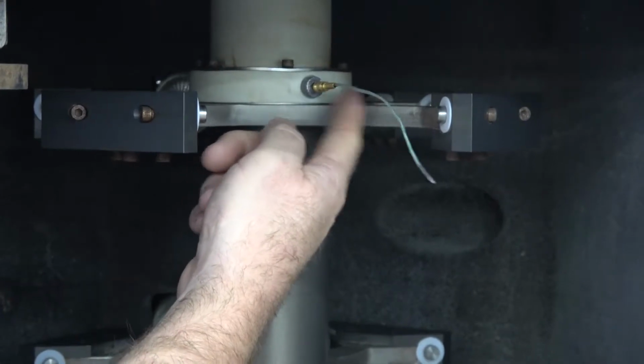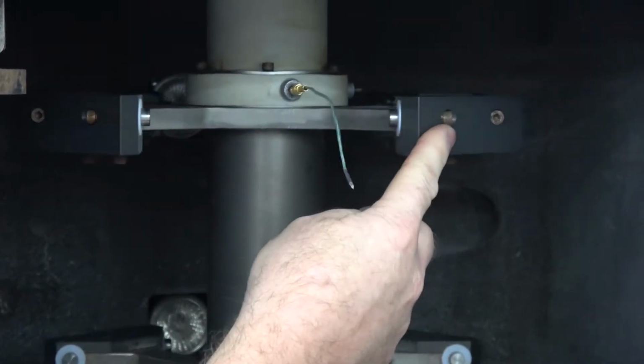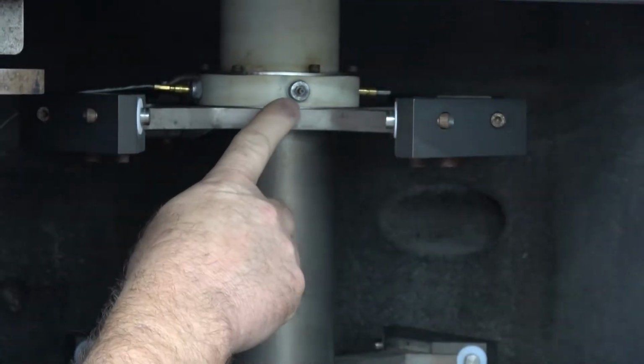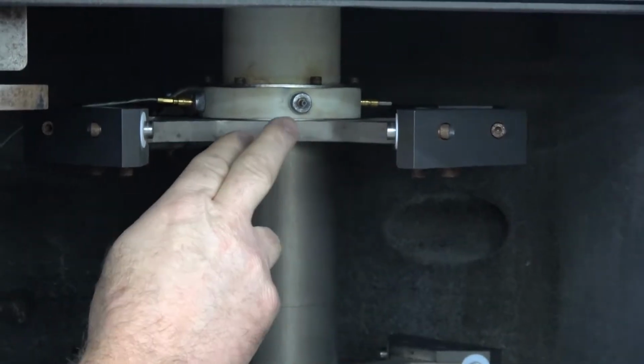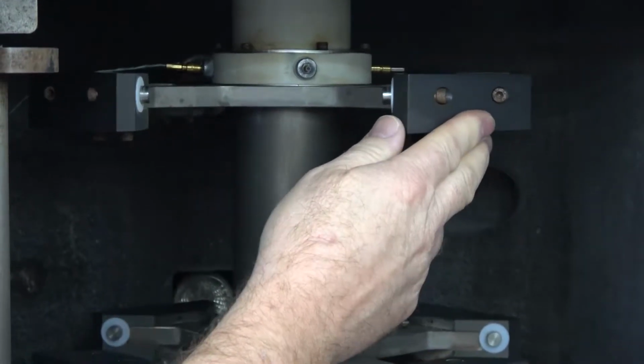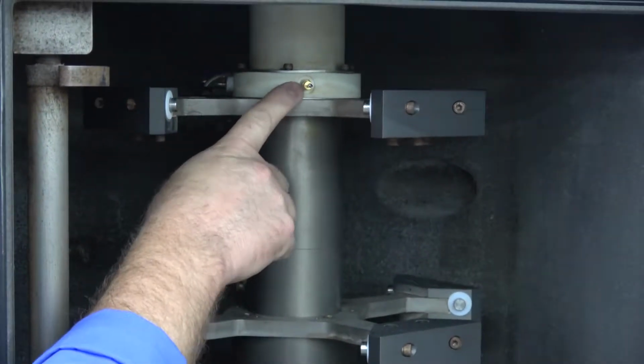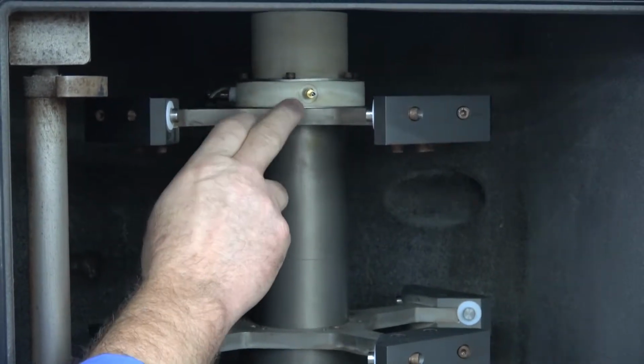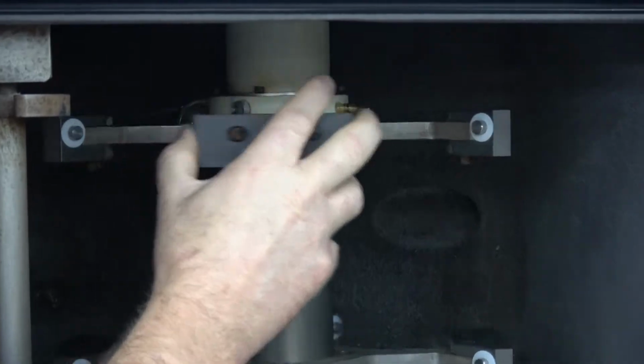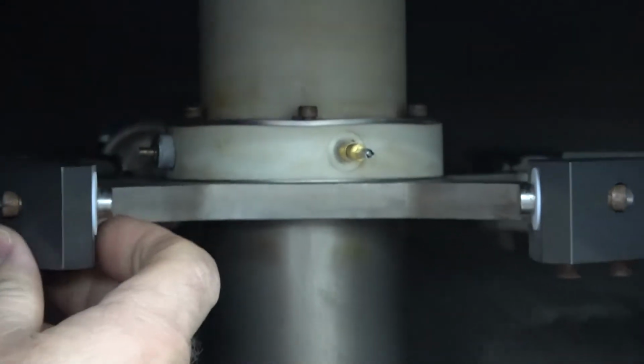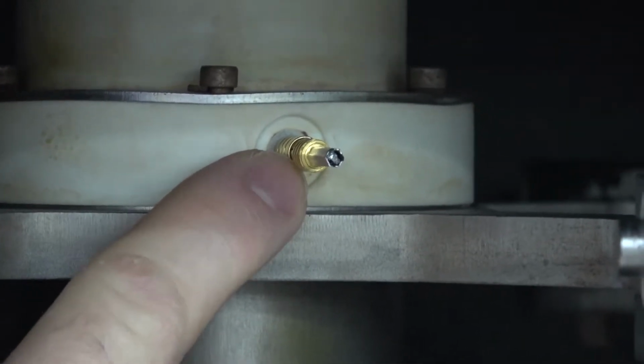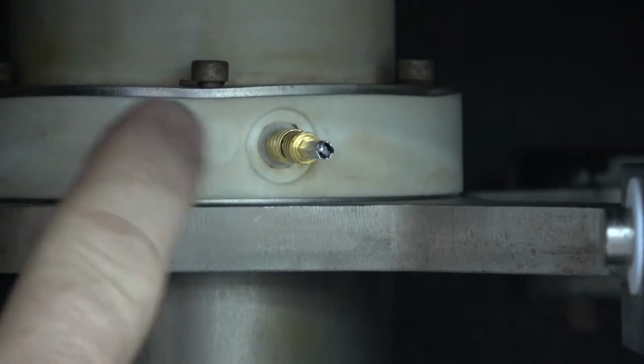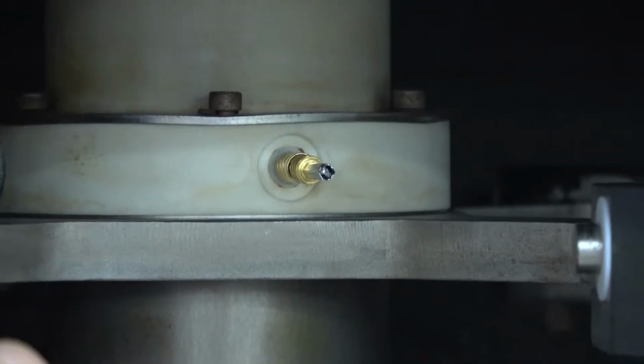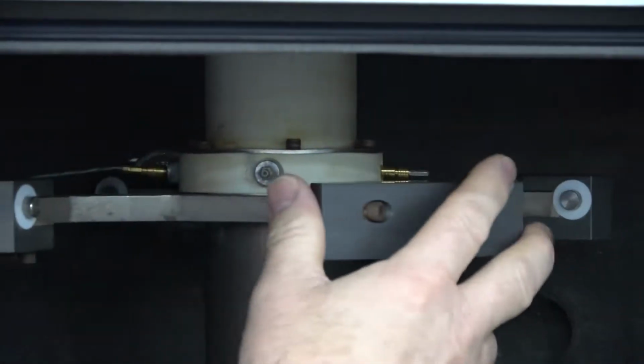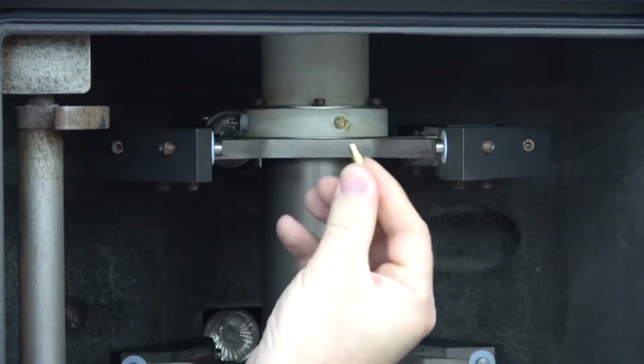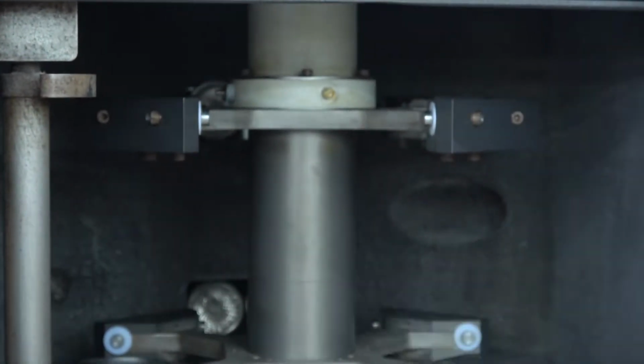So this does have the sample probe that will monitor the sample, and you can plug it in there, or you can plug it in over here on this one. So it has 2 options, or you can run 2 at the same time if you wanted to get another one and run that in. Now the third port here, I actually had to replace this because it was completely corroded. And because it was corroded, these plug-in ports wouldn't even work. And the reason they don't work is because you need this connector plug that actually makes the contact for the system inside. And the reason that they even have this here is for calibration purposes. So if you wanted to calibrate these probes here, what you would do is you would take this plug out like this. Don't lose it, because you need this to actually run that.